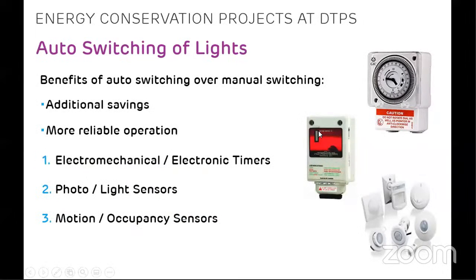Up till here I've talked about replacing lamps, replacing ballast or using solar energy. But we can also conserve energy in existing systems by proper switching of the lights. Most of the street lights or most of the lights in our area were earlier switched on manually. So to get additional savings and also for reliable operation, we used different types of auto switching systems. The benefit of this auto switching system is that not only is energy saved, but the operation is also reliable. For example, earlier we were dependent on some human or operator to switch the lights on and off. Now they are switched on and off at the required time automatically, without any requirement for an operator.